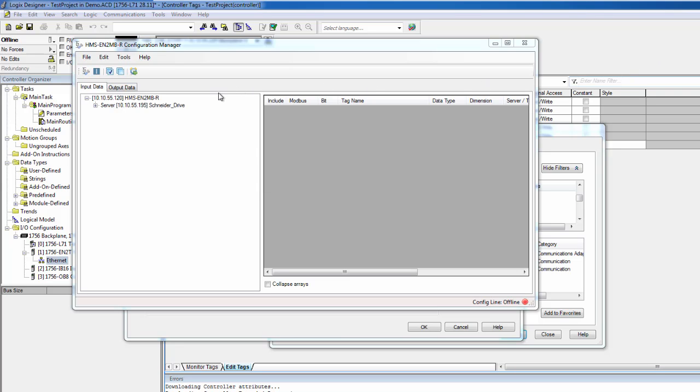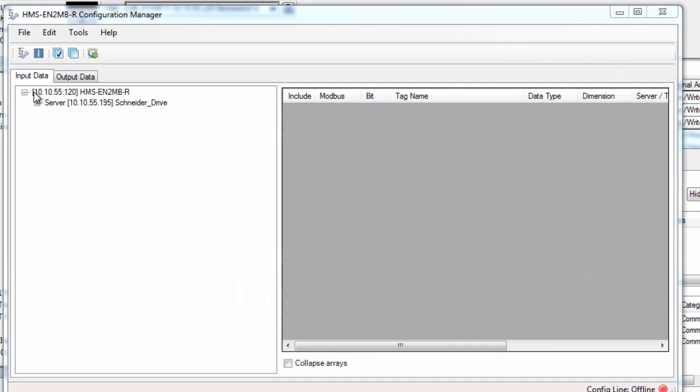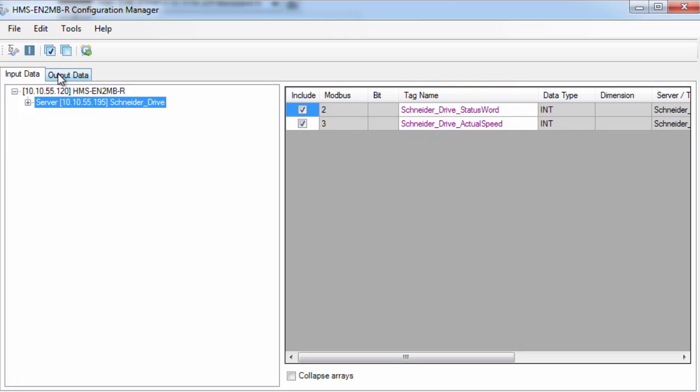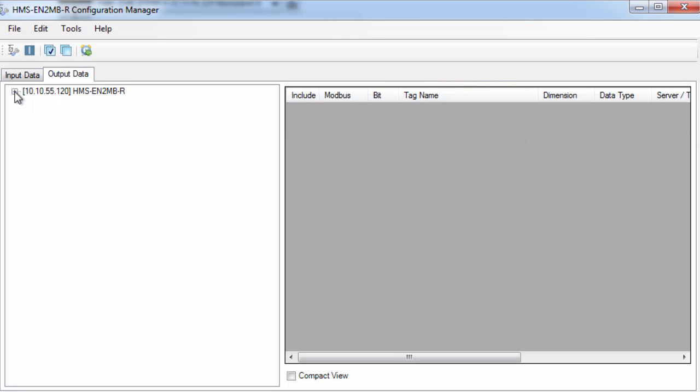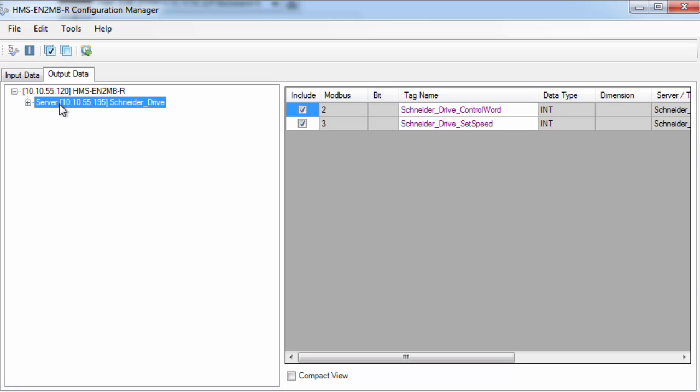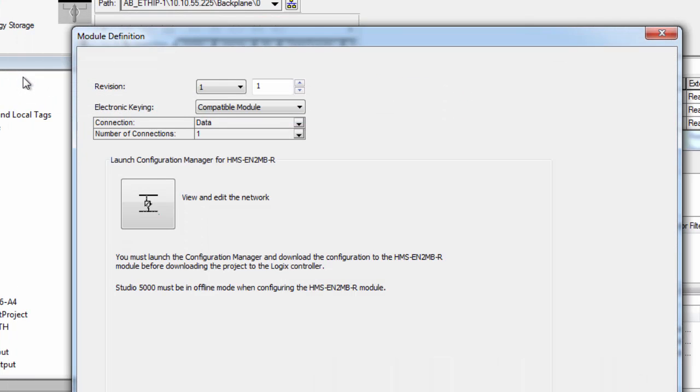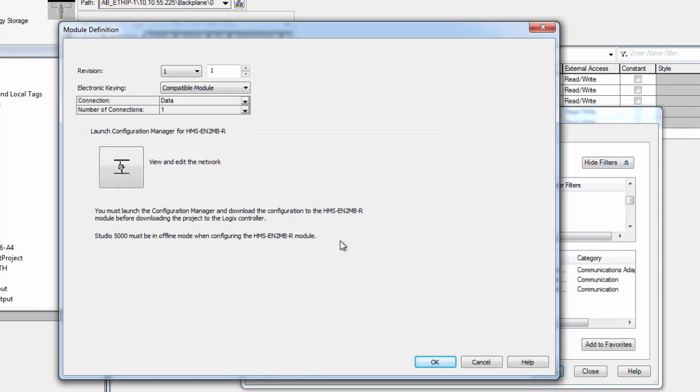I can now check the tag editor and see the inputs I've just created: the Schneider Drive status word and actual speed. And in the Output tab, I can see the output tags towards the drive, control word and set speed. I now exit the tag editor and click OK.